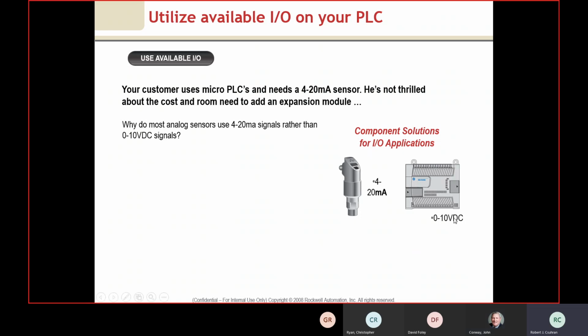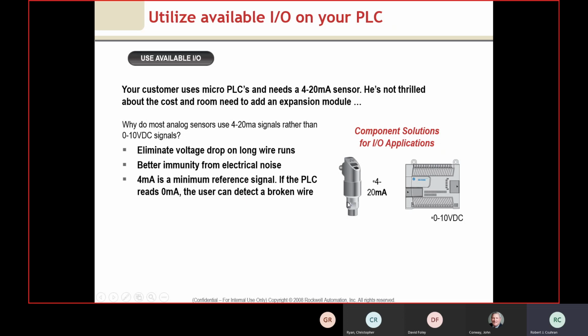Sometimes we're stuck with a situation where, in this case, this unit here has 0 to 10 volts DC, and the signaling device coming into it is 4 to 20. A couple ways to do this: we'd have to go out and buy another I/O module if that was available, or we could add a signal converter to help us with that.